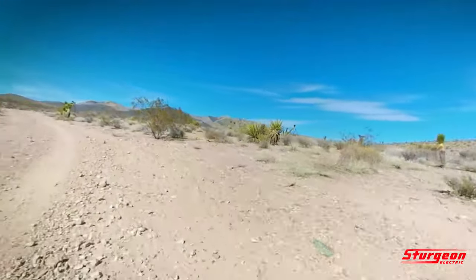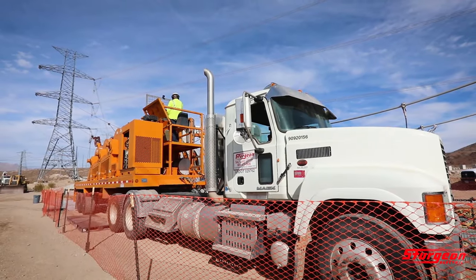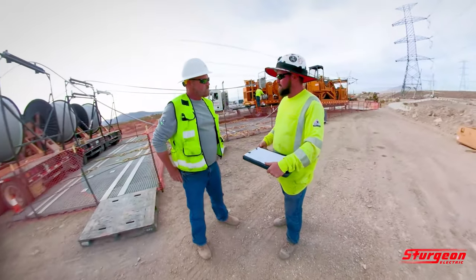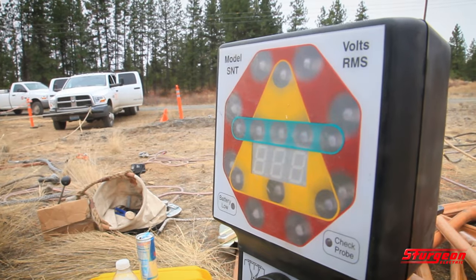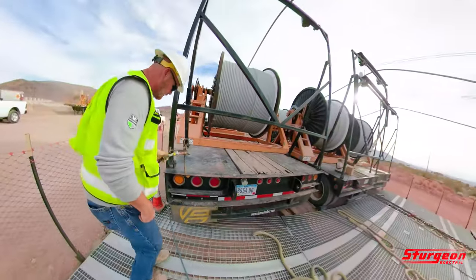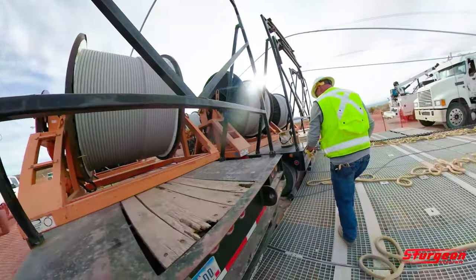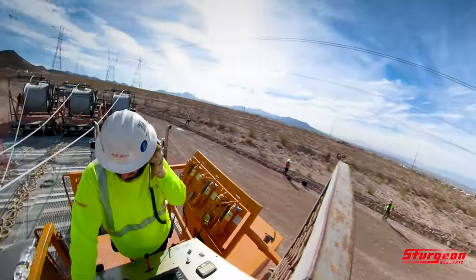On top of that, the dry desert dirt, while easy to drive on, is not the greatest when it comes to grounding lines and equipment. A project-specific safety plan was developed which took everything into consideration: the soil, the terrain, the wind, the wire, tower types, crossings — you name it. Step-touch meters were used to bolster grounding capabilities. EPZ zones set up around each wire pull site were routinely inspected by MYR Group safety professionals to provide maximum protection for line workers and equipment operators.